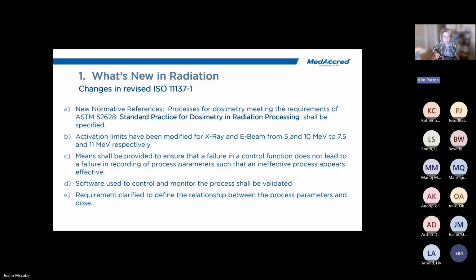To avoid this, you must decouple control systems from monitoring and recording systems, looking at things like physical and logical independence, assuring they don't have the same components—so separate sensors, independent data paths, and power supplies. Also looking at redundancy and logic: if a single sensor fails, which one is telling the truth? So 2 out of 3 logic can be used, where you have 3 sensors and the system can compare readings.